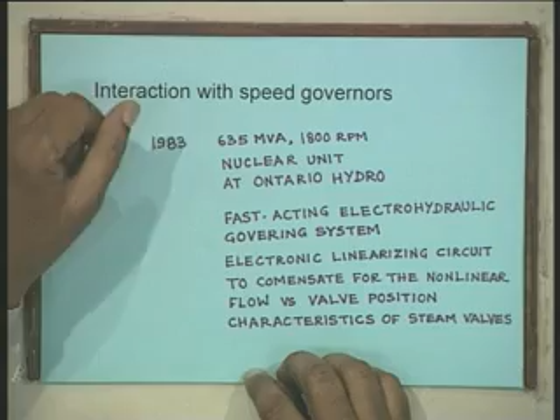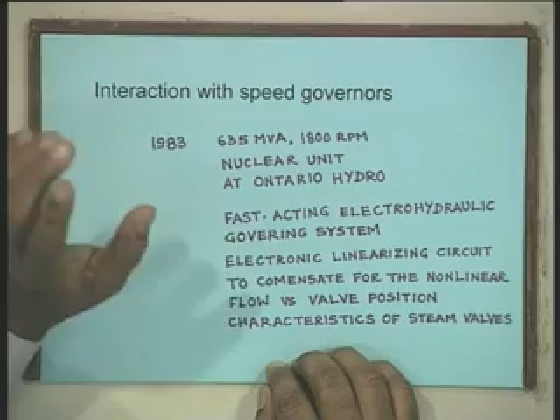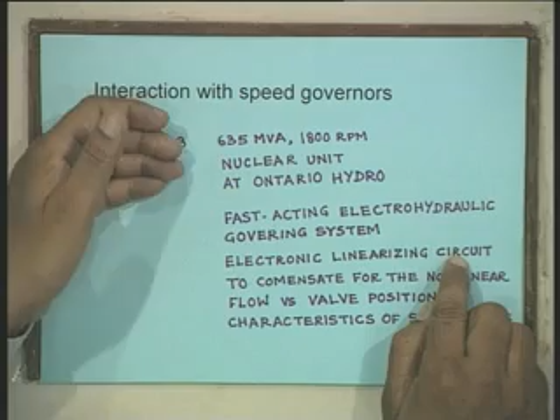Then it was observed that when this machine, which was under commissioning, was loaded to 100 megawatt load, its capacity being 635 MVA, vibrations of the steam valves were experienced, and immediately they looked into the electronic circuits and some retuning was done. With that retuning, they could load up to 475 megawatt, and at that loading condition again the steam valves were vibrating. When it was examined in detail, it was found that the electronic linearizing circuit was behaving in a different fashion at that particular frequency. A particular frequency was sensed, because the governor senses the speed of the rotor, and for sensing the speed of the rotor, the speed sensor is mounted on the high pressure end of the steam turbine.